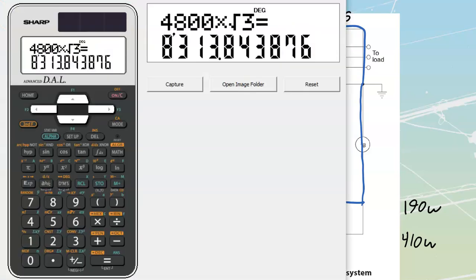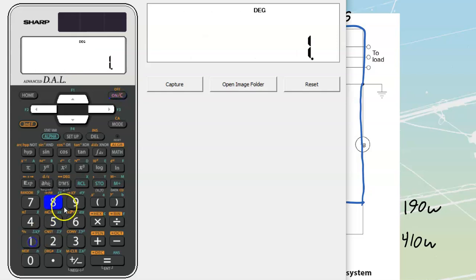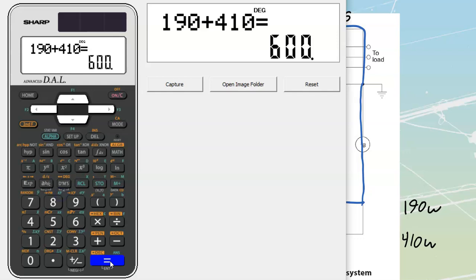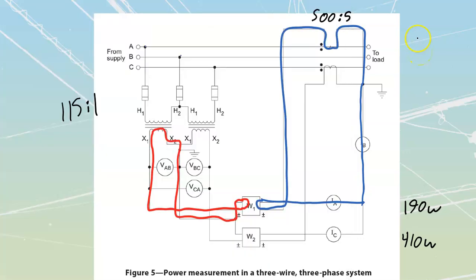Let's start by doing the 190 plus 410, which gets me to a value of 600. So we're going to come back to this one over here. We've got 600 watts multiplied by my overall ratio, 500 over 5 and 115 over 1. So we are going to just multiply those together.